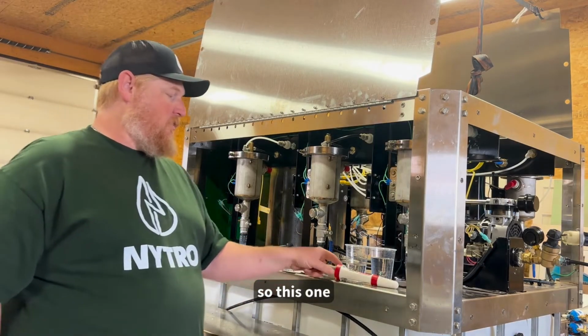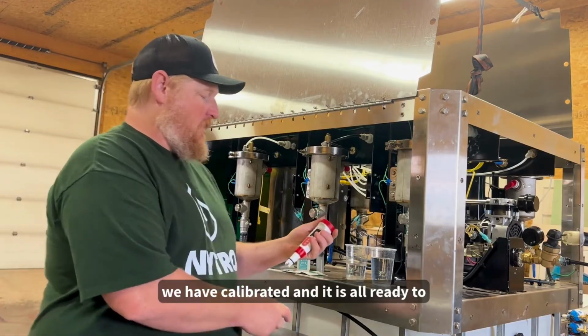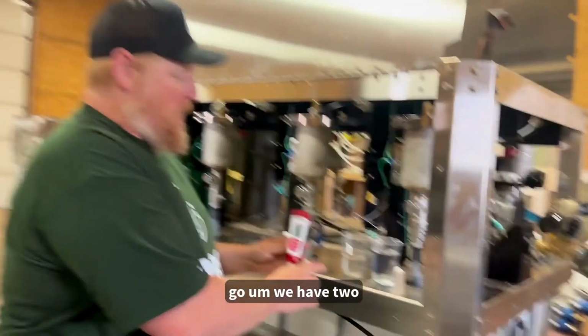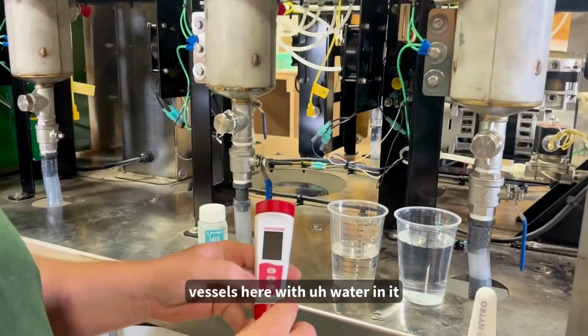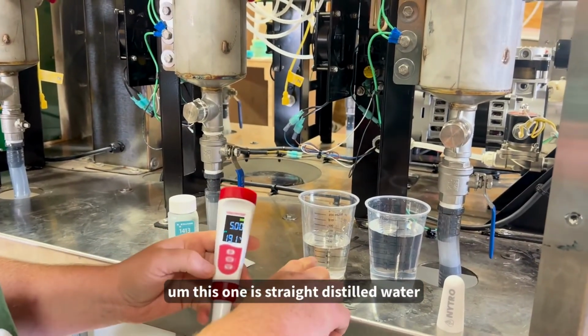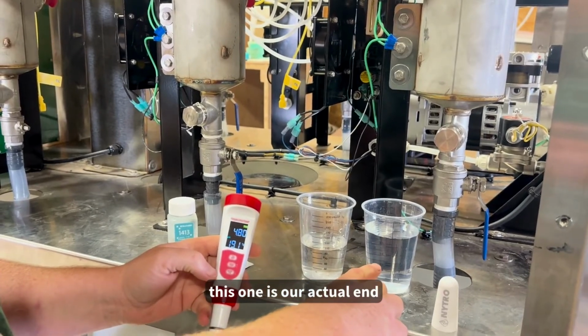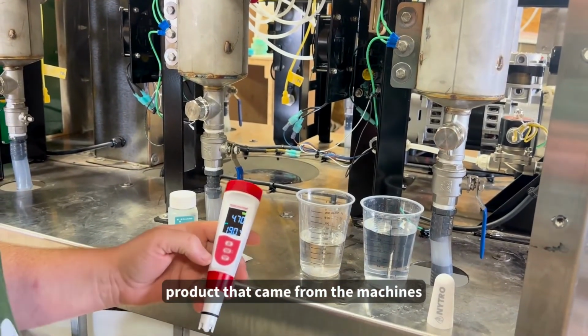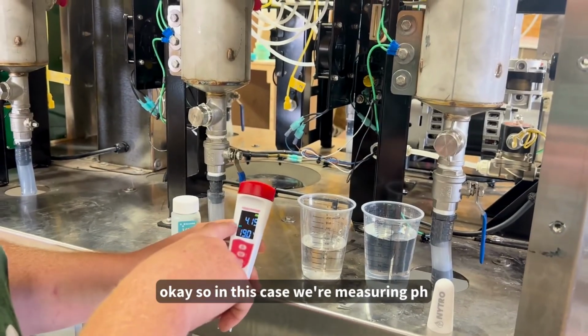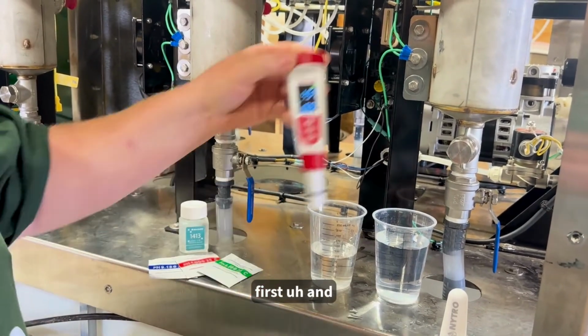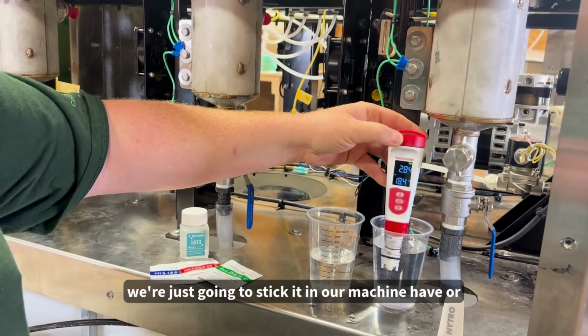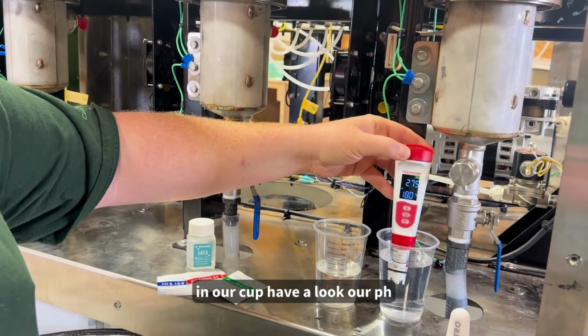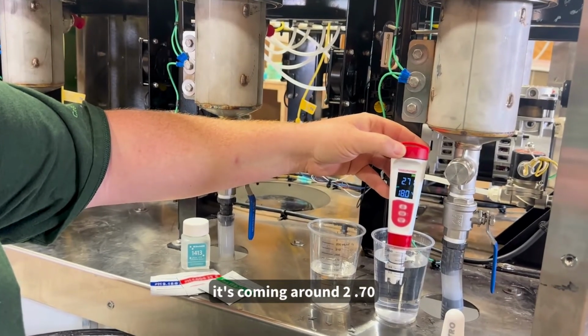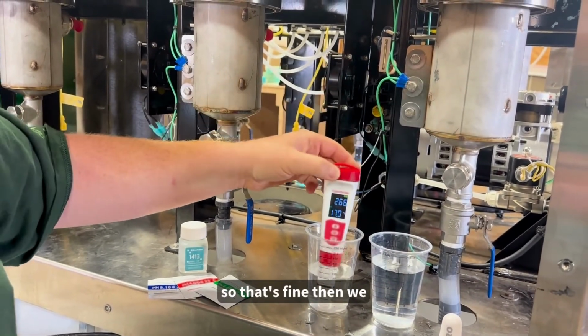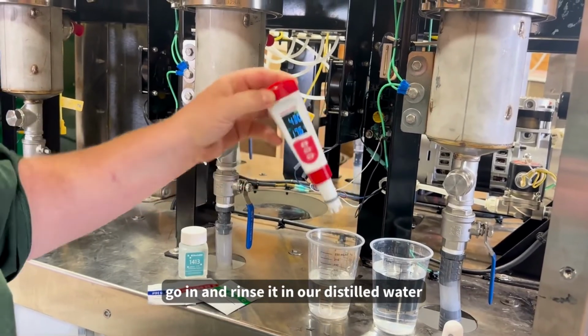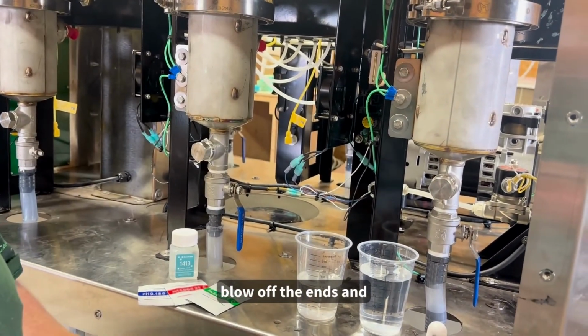Okay, so this one we have calibrated and it is all ready to go. We have two vessels here with water in them. This one is straight distilled water. This one is our actual end product that came from the machines. In this case, we're measuring pH first, and we're just going to stick it in our cup and have a look. Our pH is coming in around 2.70. So that's fine. Then we rinse it in our distilled water and blow off the ends.